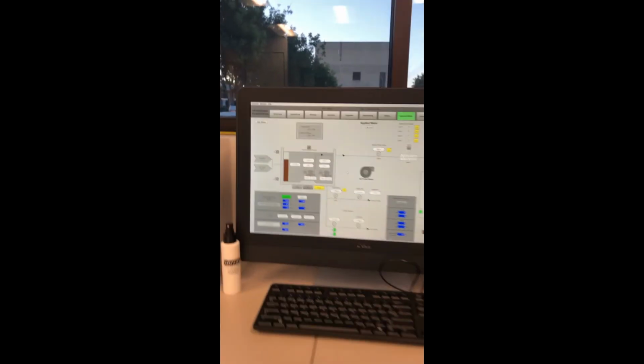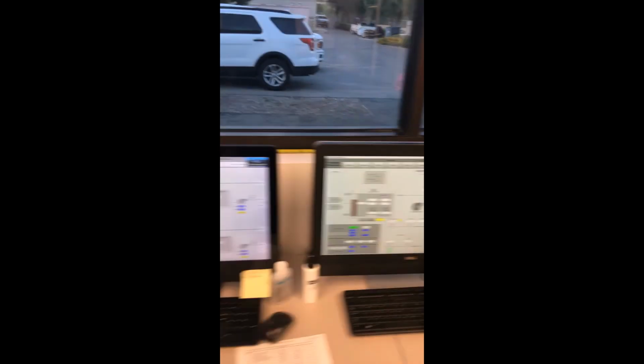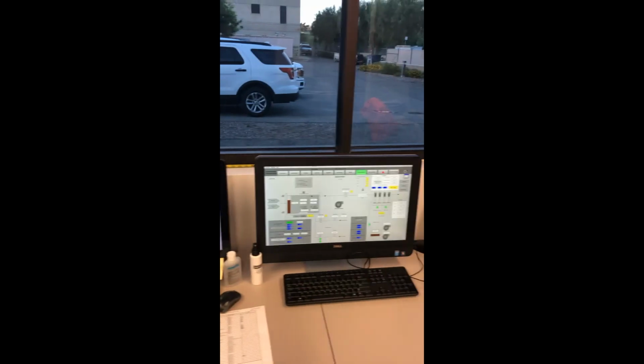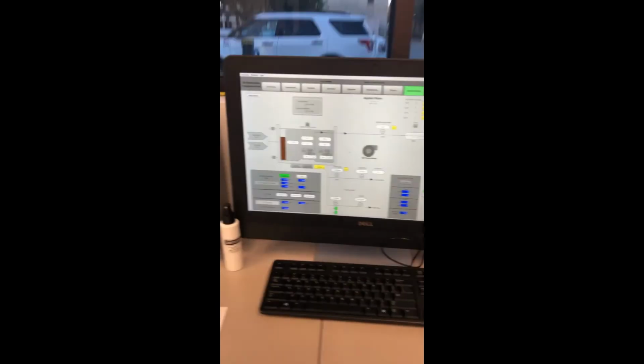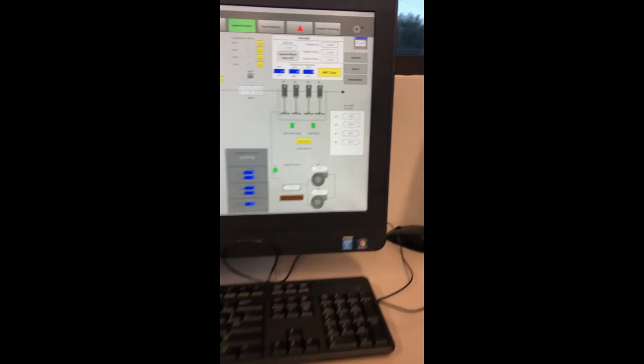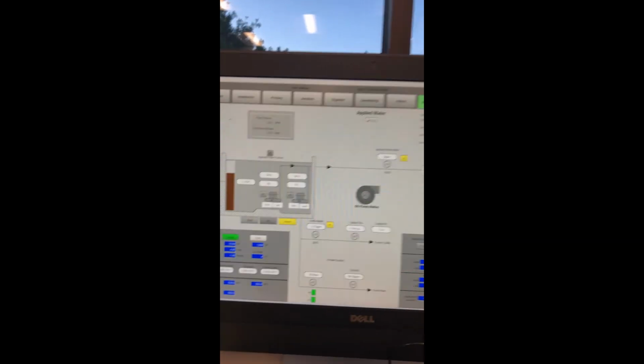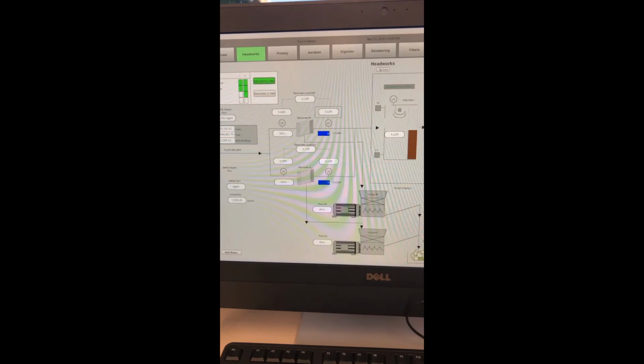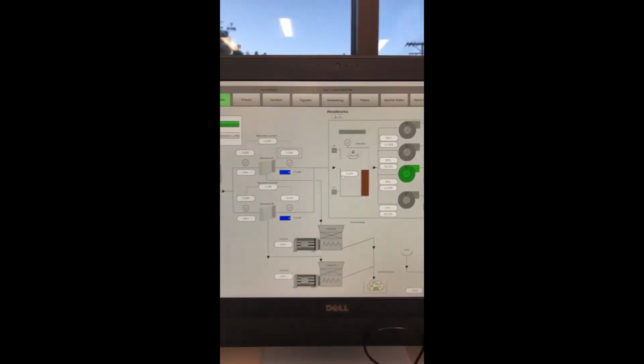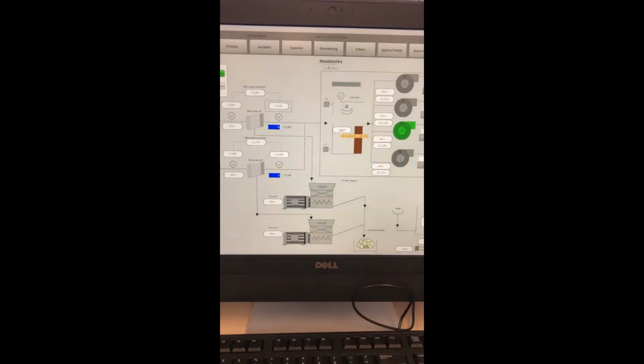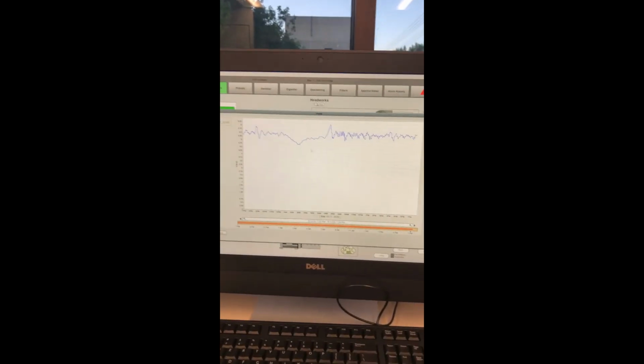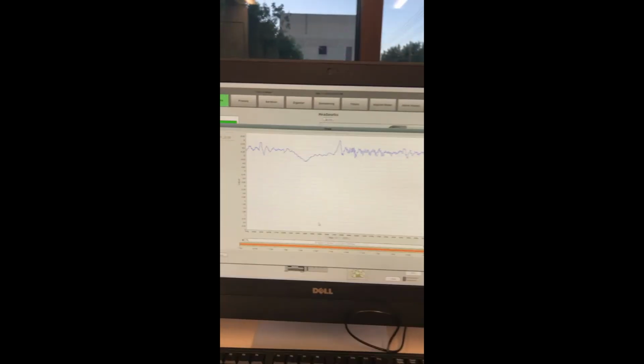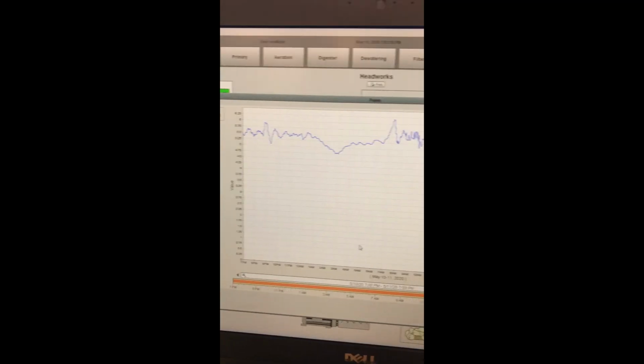So this is our SCADA screens, and you have two of them here so that two people can work. Oh, the trending. You can go to any of these flow meters here. Let's find one that's got a lot of flow going through it. Well, let's take a look at the level. If you double click the level, it gives you a nice trend, and it'll tell you what the level's been over the last 24 hours. That's what the level has been in the influent wet well.